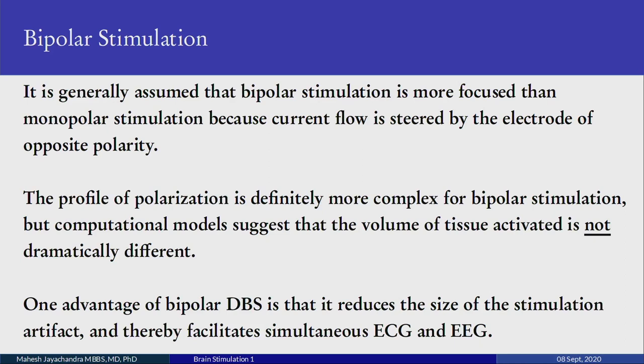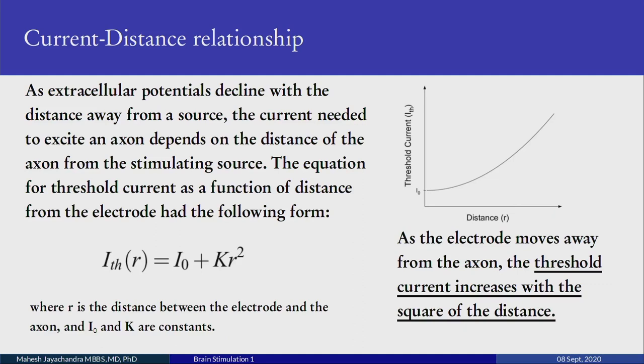One major advantage of bipolar deep brain stimulation is that it decreases the stimulus artifact, allowing simultaneous recording of ECG and EEG. Regarding how far the electrode should be from the site of interest: extracellular potentials decline with distance from a source, so the current needed to excite an axon depends on the distance from the stimulating source. The threshold current as a function of distance follows the equation I(r) = I0 + k·r², where r is the distance between the electrode and the axon, and I0 and k are constants. As the electrode moves away, threshold current increases with the square of the distance.